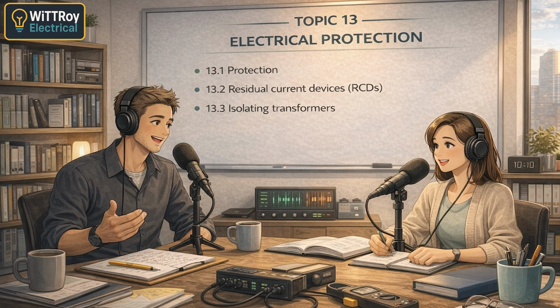Ah, okay, heat in the cable. That's right. Heat is the key issue here. And heat damages insulation. Exactly. Insulation can soften, melt, or even carbonize. And once insulation is damaged, metal parts can become live. Correct. And that leads to fire risk and electric shock risk.